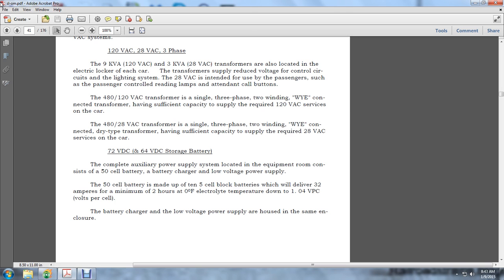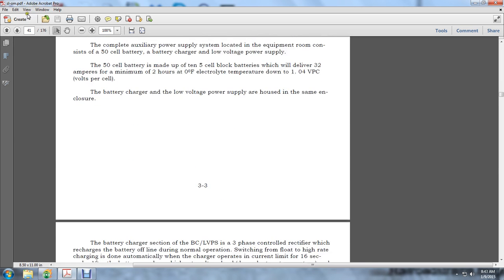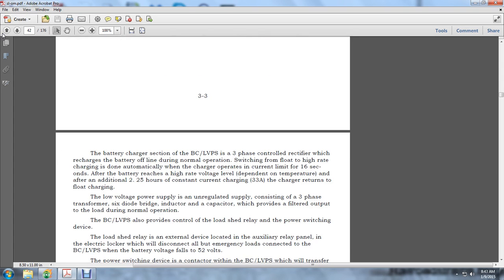The battery charger of the low voltage power supply is housed in the same enclosure. The battery charging connection with the LVPS is a three-phase controlled rectifier that recharges the battery offline during normal operation, switching automatically to the high rate of recharging with the charge operation. The current limit is 16 seconds after the battery reaches the high rate voltage level, depending on the temperature, and an additional 2.25 hours of consistent current charging of 33A, the charger returns to float charging.